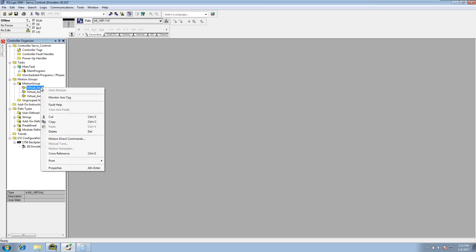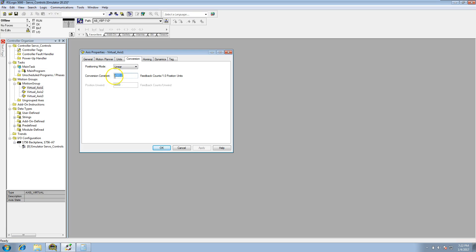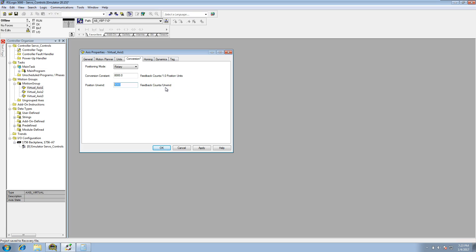On virtual axis one, we'll go to Properties. The first thing is positioning mode — most likely it will be in linear mode. In linear mode, all that is in play is the conversion constant itself: counts divided by position units. For rotary mode, we have the conversion constants and then the position unwind. To do the equation, you cancel out the feedback counts on both sides, so it would be position units divided by unwind.